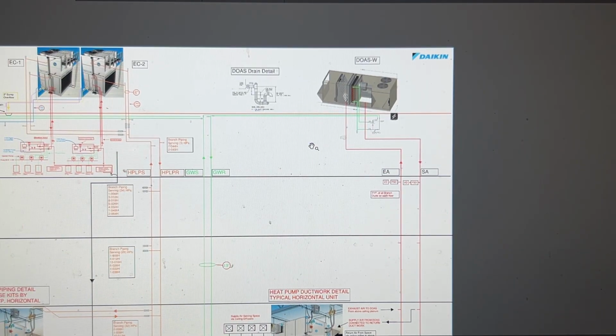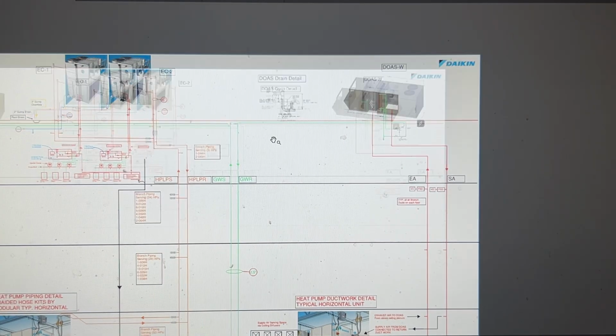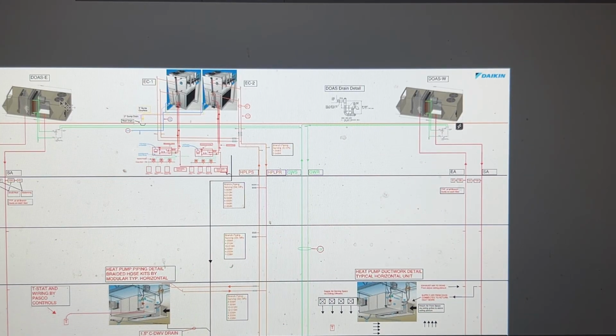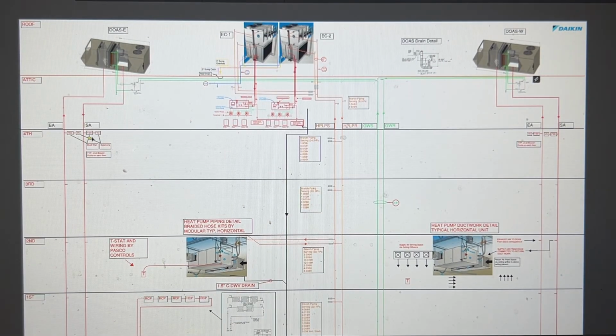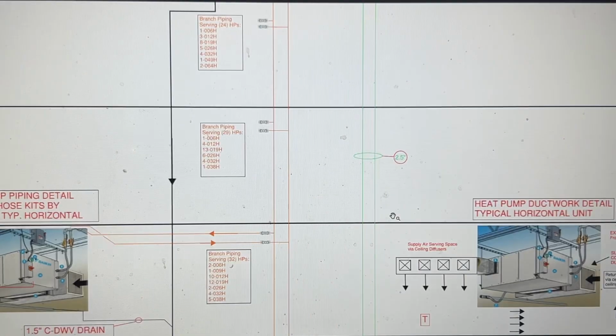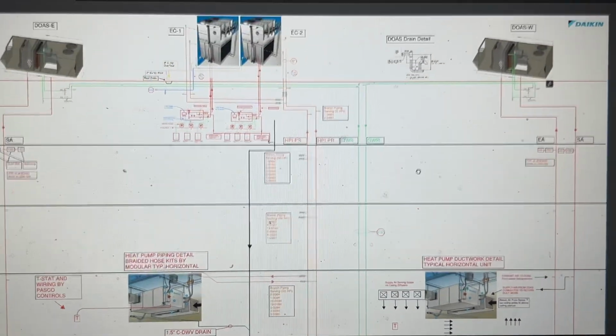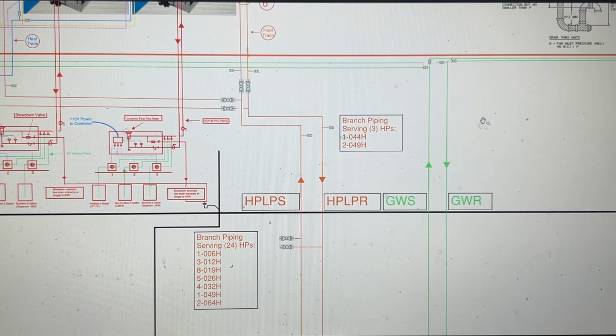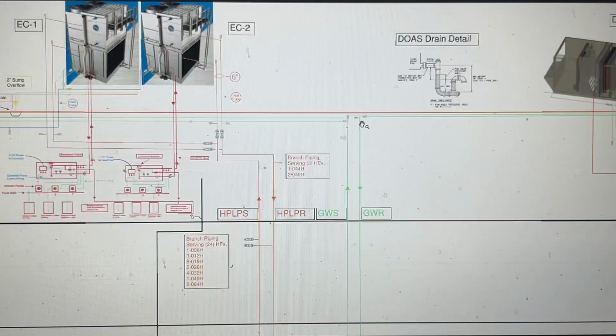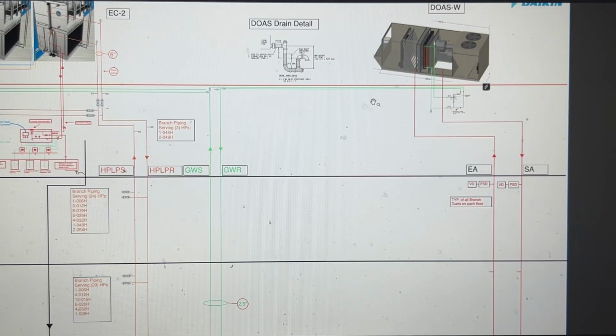All right, on the piping end of this, we have glycol supply and return coming from the mechanical room in the basement, which is what's represented here. Like I said in the beginning of the video, we had 2 of these DOAS units, one on each side of the building. So they're both replica installations on each side. For the supply and return piping, we have 2.5-inch welded pipe that gets up into this attic space and branches off each way to go to the rooftop unit.